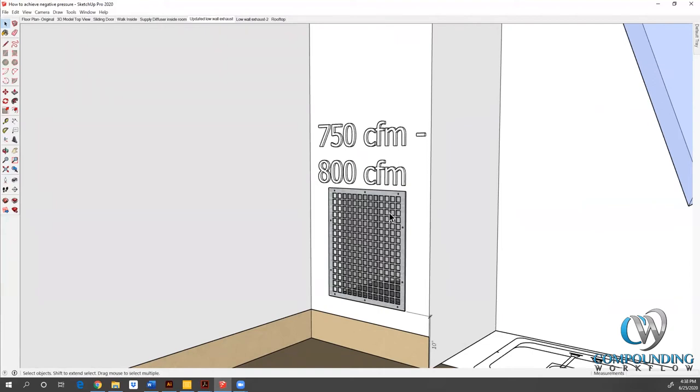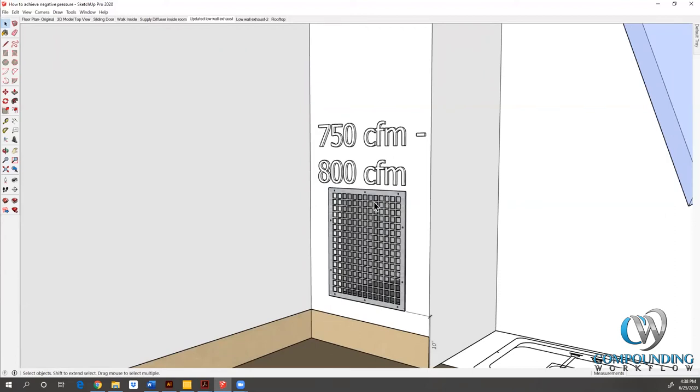I like to tell folks that to achieve negative pressure, your percentage, because 0.01 inches of water column is not actually a lot of negative pressure, is about 15%. Well, I've come to find that that's not necessarily true because based on the cube, based on the ductwork, based on the height of the roof, based on all of these different factors that are sometimes not within our control, that 15% is not a good rule. But we do sometimes talk about that. I've seen it as high as 40% to achieve such a small minor negative pressure of 0.01 inches. But in that scenario, remember I told you we put about 1200 CFM on the makeup air unit to supply the air.